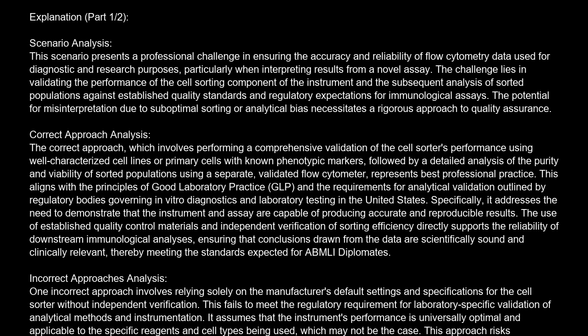One incorrect approach involves relying solely on the manufacturer's default settings and specifications for the cell sorter without independent verification. This fails to meet the regulatory requirement for laboratory-specific validation of analytical methods and instrumentation. It assumes that the instrument's performance is universally optimal and applicable to the specific reagents and cell types being used, which may not be the case.